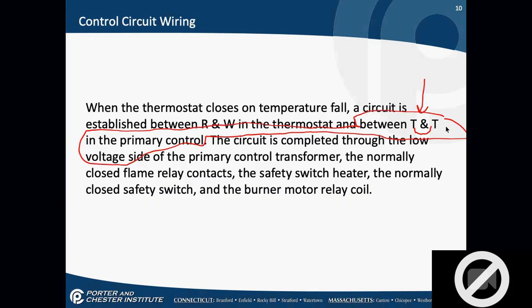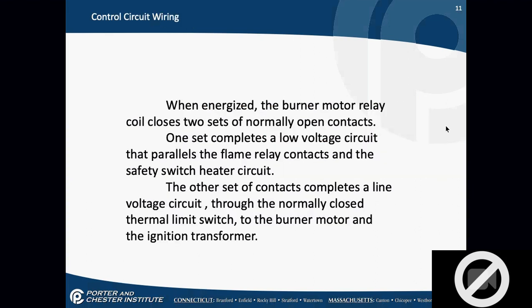The circuit is completed through the low voltage side of the primary control, and it actually energizes the burner motor. Okay, basically, as long as all the safeties are closed, it turns on the burner motor. Okay, it also turns on the ignition transformer, as long as my high limit switch is closed. And again, we still have to talk about the primary control. But the primary control is what energizes the burner motor and the ignition transformer.